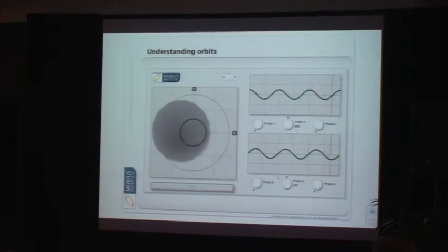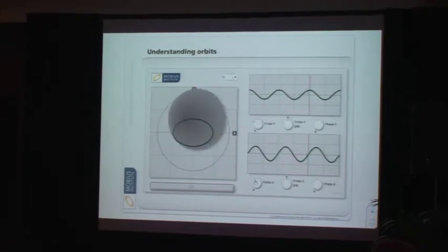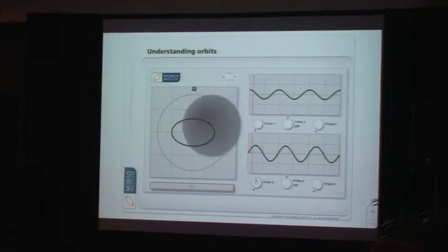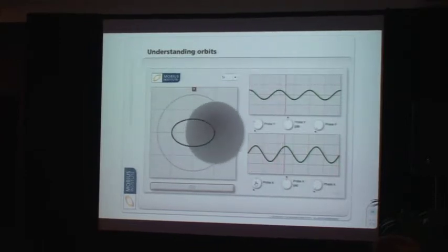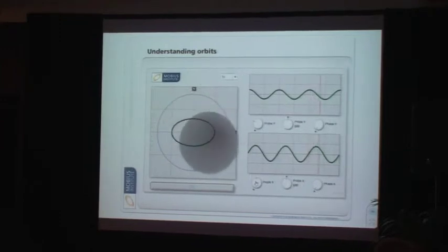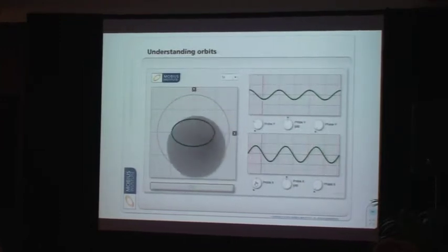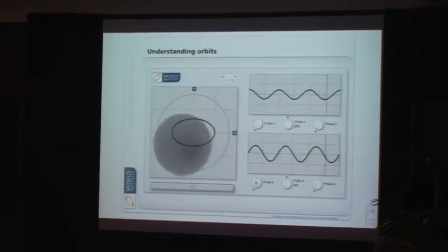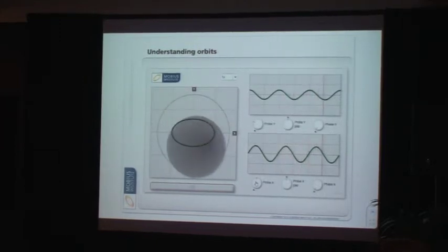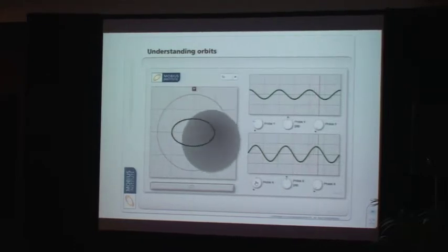Now, of course, we can have a little play with this. If I experienced a higher amplitude vibration in the X direction, that would tell me that the shaft is not moving in a circular motion. It's actually elliptical, moving more like this. And that's more typically what you're going to see, because the shaft is freer to move horizontally than it is vertically. In a moment, we'll talk about bearings just a little bit. If you've got a round bearing, you get one sort of typical orbit shape, but with tilt pad bearings or lemon or elliptical bearings, there's more freedom to move, less stiffness in that horizontal plane, and therefore it can move more.